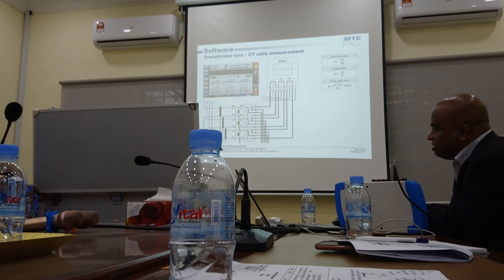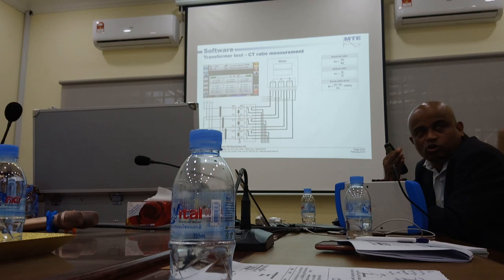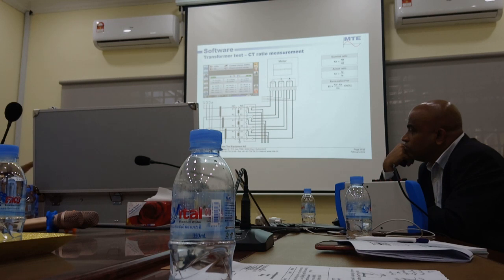If you want to actually test the CT, you have to use a CT analyzer, like what Omicron and others have. When I check in the Omicron, the diagram is like this one. It measures the CT burden of the load, not the real electric burden of the CT. I don't know which equipment you use. Sometimes I'm afraid that our specification for the CT is, for example, 15 VA, but actually maybe the supply is lower than this.